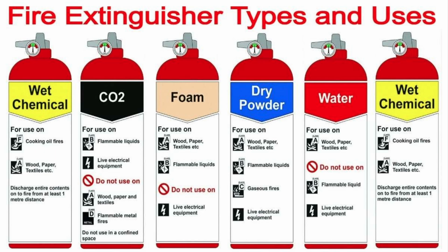Where this is not possible, the operator should stand well back and allow the foam to gently fall onto the liquid surface. Direct discharge of the foam into burning liquid should be avoided. Then we got dry powder, just right of that. The approximate effective range is 13 to 16 feet. That's been all of them so far. That's water, foam, and dry powder are all 13 to 16 feet.